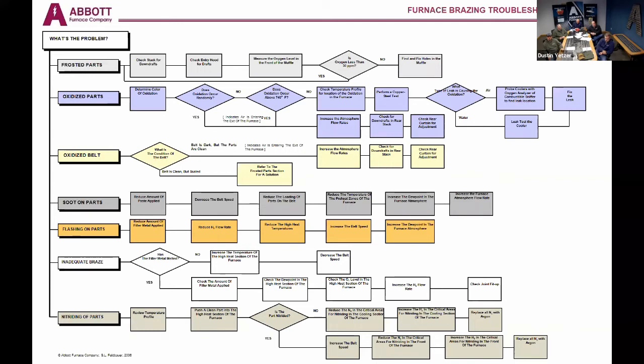The other point about brazing that comes up a lot is joint fit. So when we're pressing a round socket into a round tube, the hole in the tube is oblong. As you flatten that round tube out, you're pressing a round hole into an oblong pocket, and joint preparation and the gap around that joint is exceptionally critical, especially for a lot of high pressure fluid applications. So those are all very common brazing failure modes. If there's a specific example that someone had, feel free to reach out and we'll do our best to help you out.